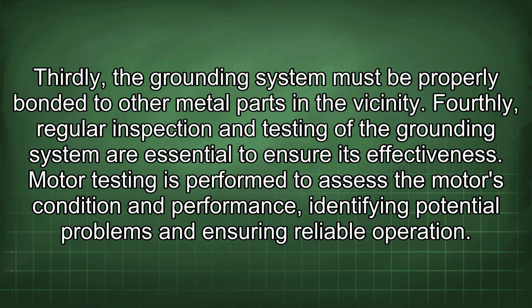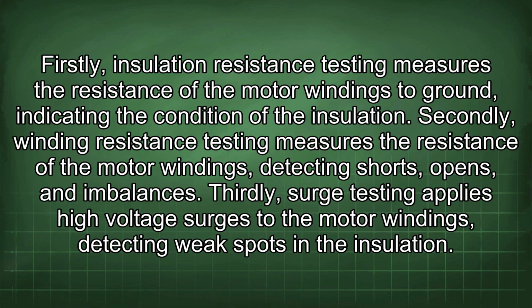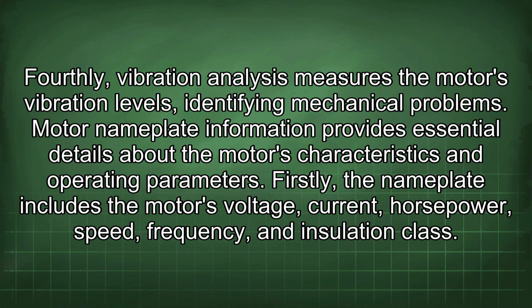Motor testing is performed to assess the motor's condition and performance, identifying potential problems and ensuring reliable operation. Firstly, insulation resistance testing measures the resistance of the motor windings to ground, indicating the condition of the insulation. Secondly, winding resistance testing measures the resistance of the motor windings, detecting shorts, opens, and imbalances. Thirdly, surge testing applies high voltage surges to the motor windings, detecting weak spots in the insulation. Fourthly, vibration analysis measures the motor's vibration levels, identifying mechanical problems.